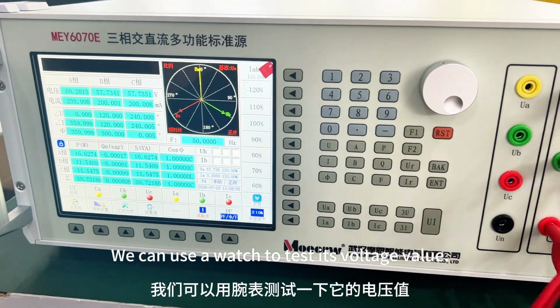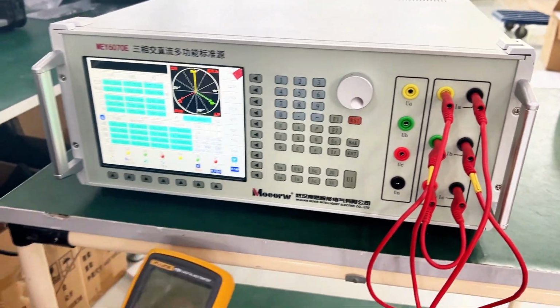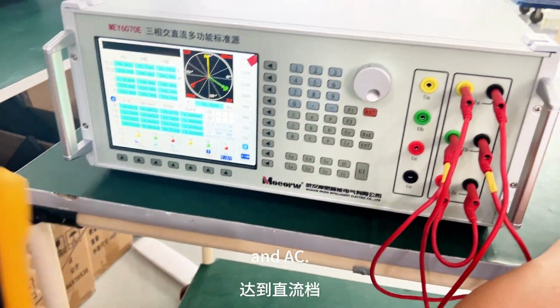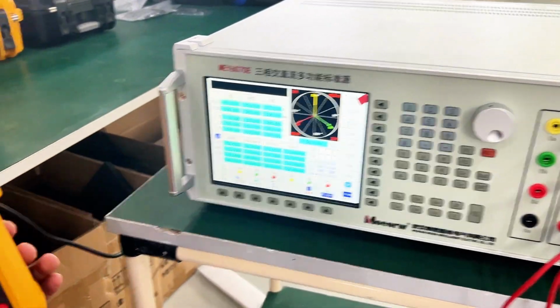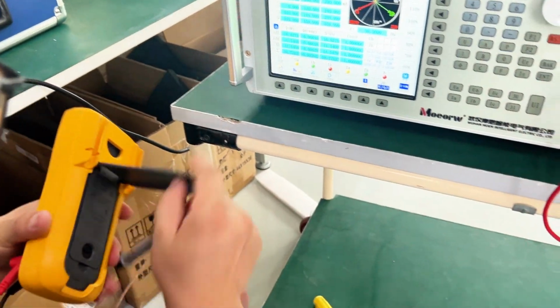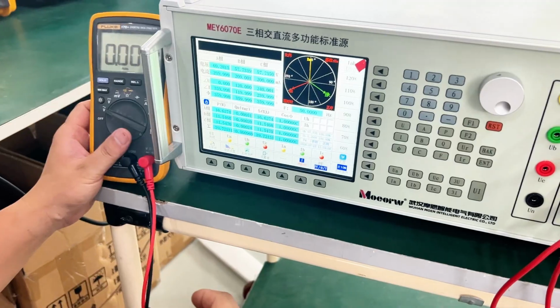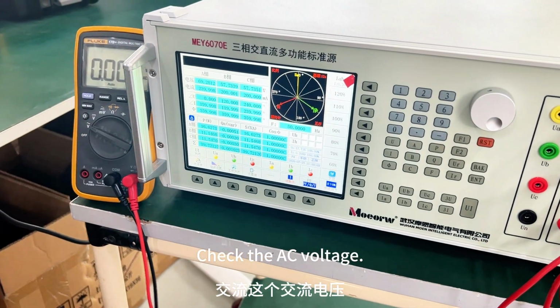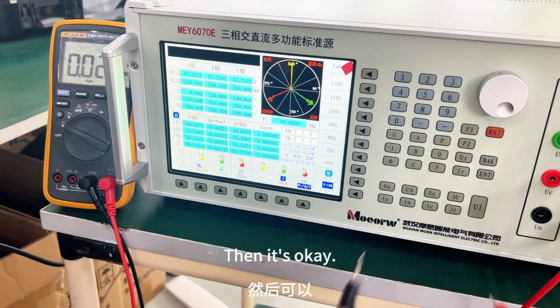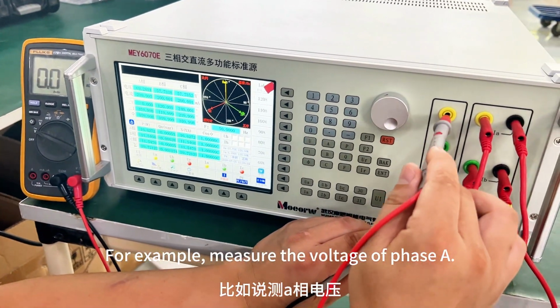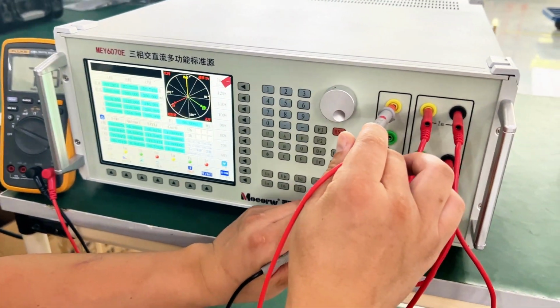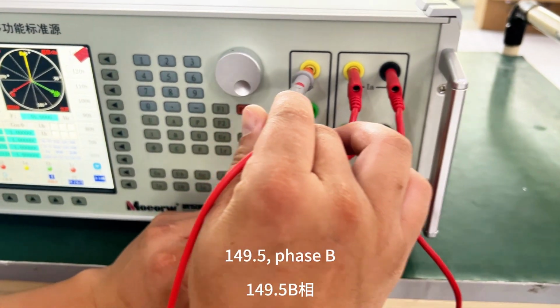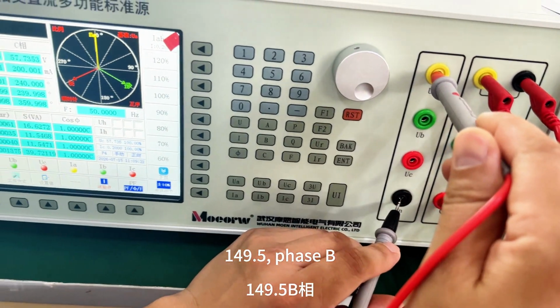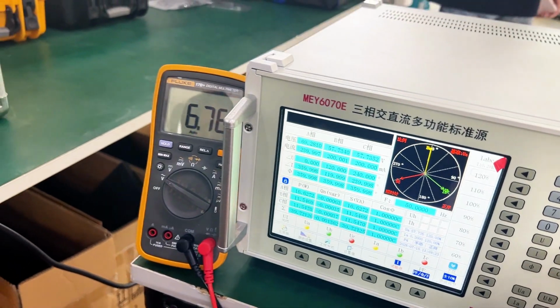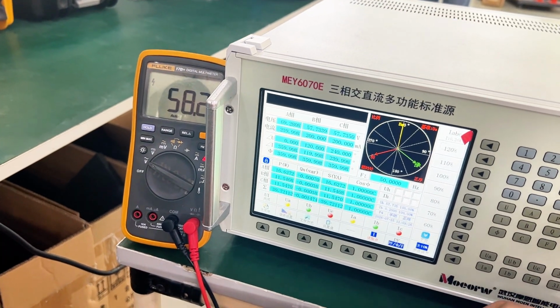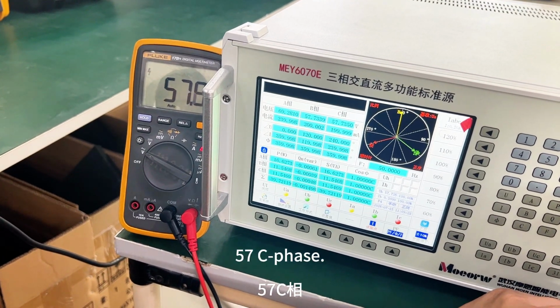We can use a meter to test its voltage value. And AC. To check it. Check the AC voltage and turn it to AC. Then it's okay. For example, measure the voltage of phase A. 149.5, phase B. 57, C phase.